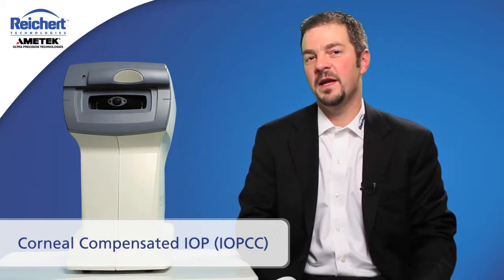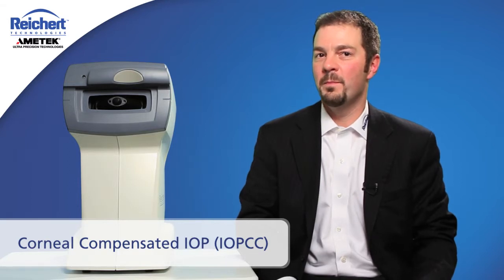Corneal hysteresis is the world's only indication of biomechanical properties of the cornea. It's that data that enables us to compensate the intraocular pressure based on the material characteristics of the cornea. The corneal compensated pressure measurement, IOPCC, is still a Goldmann correlated pressure measurement. If I were to give you a tonometer that was the most accurate tonometer in the world but the average reading from that device was 25, no clinician would know what to do with that information. We went through painstaking efforts to make sure that the IOPCC measurement still agrees with Goldmann on average, but lacks the corneal contamination that plagues Goldmann tonometry.